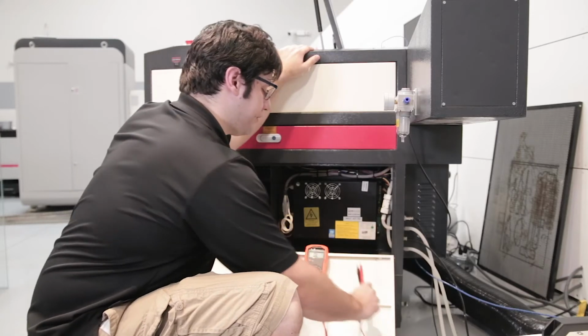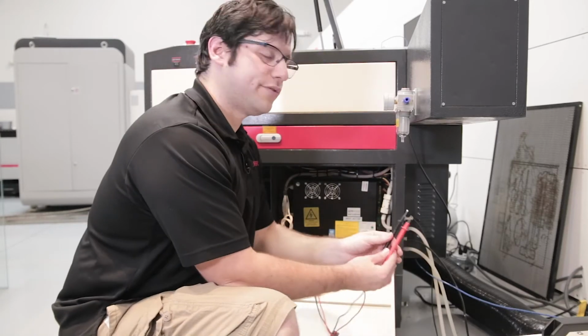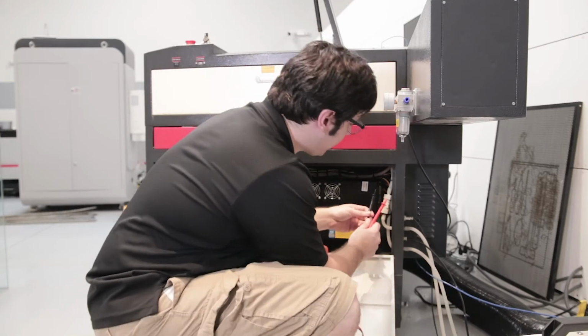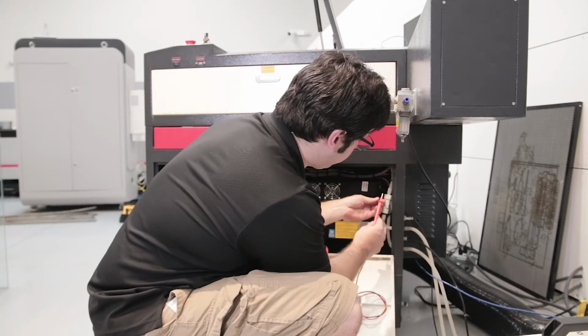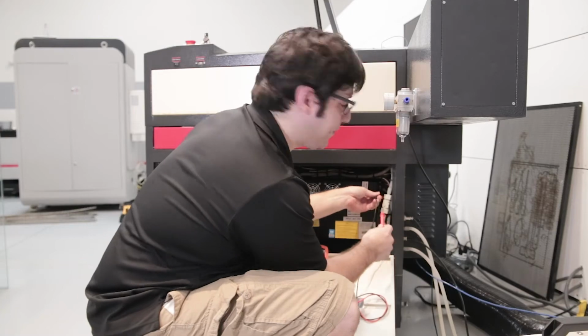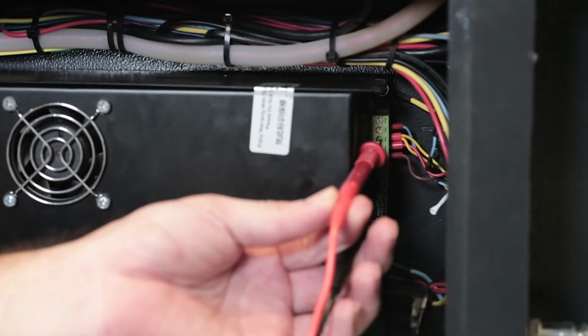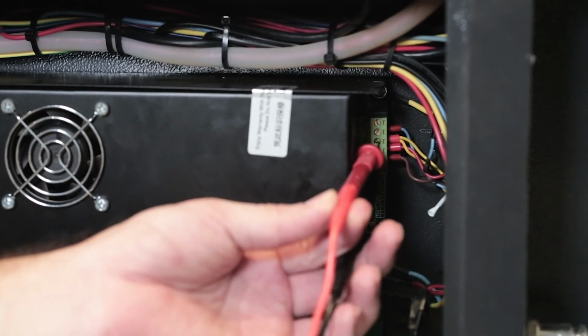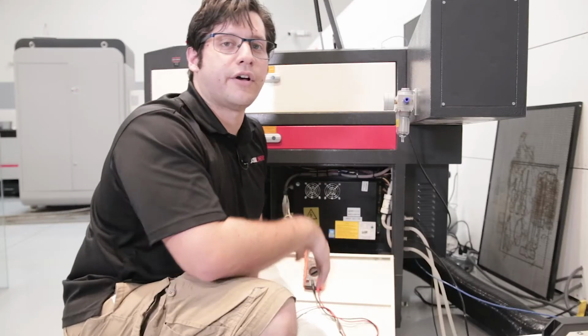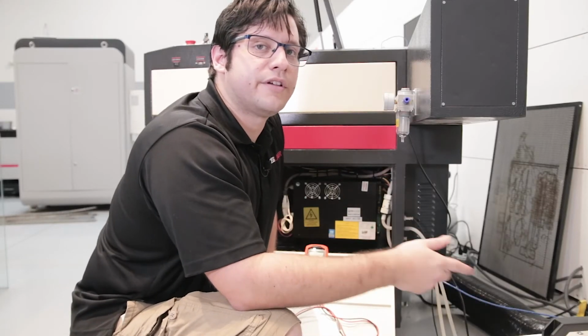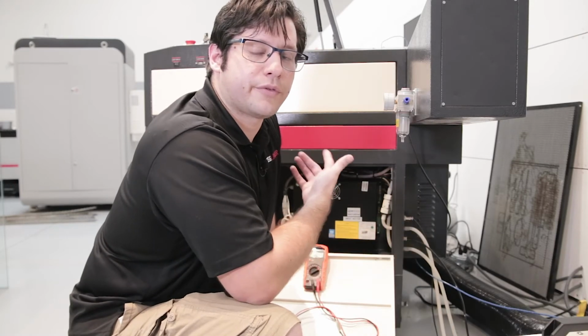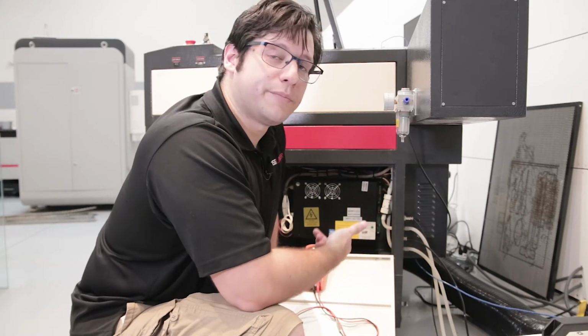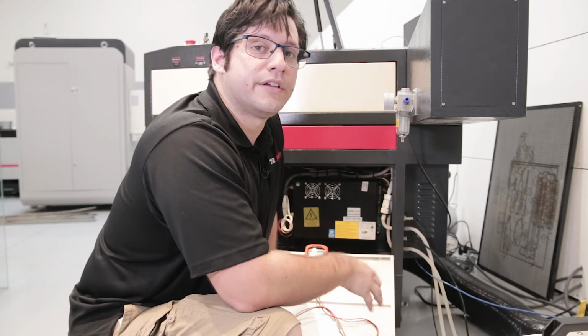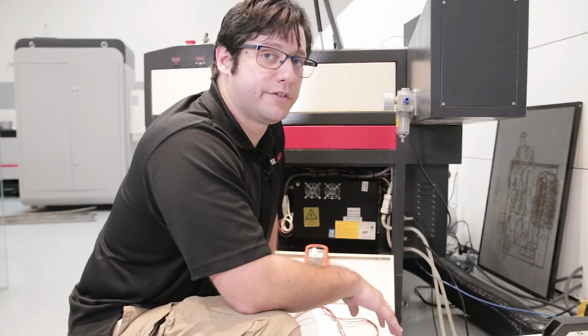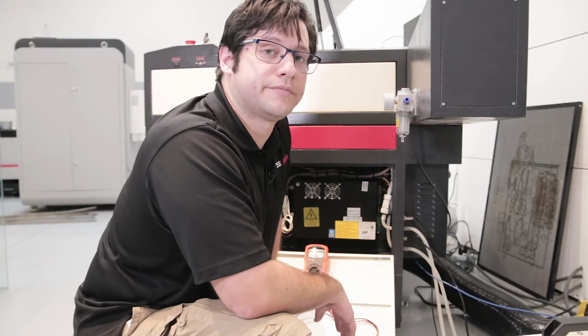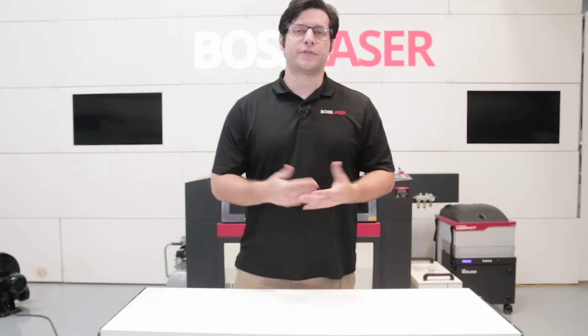So you're going to take your multimeter and place your prongs, one on 3 on the 6 pin here, and then one on 4. Now when you have them both on there, you want to make sure that all your interlocks are on, so your chiller's on, your door's closed for your door interlock. And once you put it on there, if you have continuity, that's good. If you don't have continuity, you want to go ahead and call tech support. And that's how you would check your interlocks with your Boss laser machine.